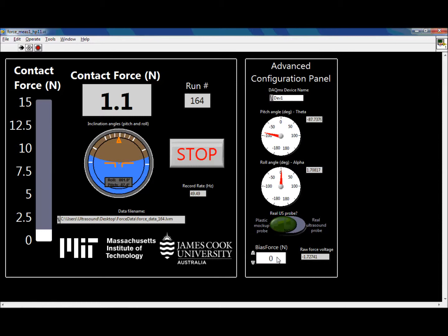So you'll see here at the bottom we have a bias force box. Now right before you're ready to begin conducting the exam, take the device and hold it in the air, not in contact with anything. So it's currently being held in the air, and we'll note that the force it's reading, the bias force, is about 1.7 newtons. So go ahead and in this bias force box, we'll type in 1.7 and press enter. Now you'll notice that the force reads basically 0. It fluctuates very close to 0. So now if we press in contact with the patient, we see the force go up and go down as it should.